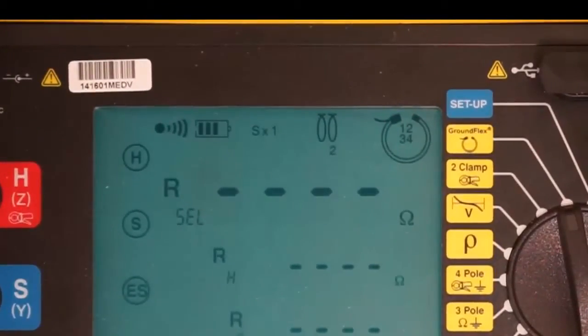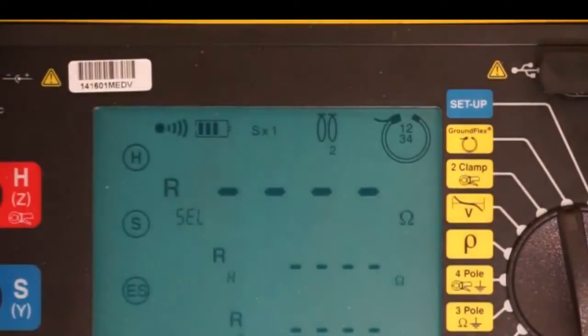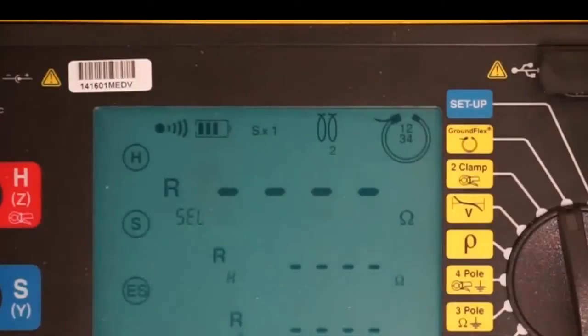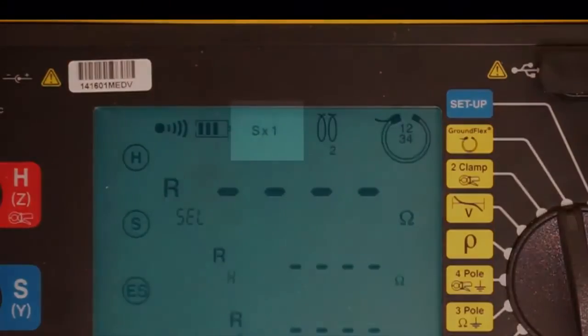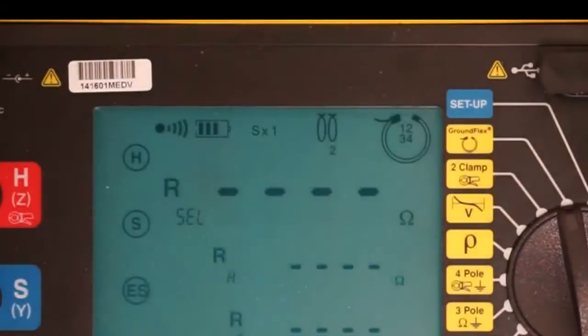In the upper right corner is the icon indicating the number of tower legs we're testing. In this case, we're testing the vector sum of all four, as indicated by the dial on the Model 6474. This should also be reflected in the icon. The next icon on the left indicates the number of times we looped our ground flex sensors, which in this example is 2. The next icon to the left indicates measurement sensitivity. In our example, this is 1, as we set earlier via the sensitivity dial on the Model 6474. If any of these icons indicate a setup discrepancy, make the appropriate adjustments now.